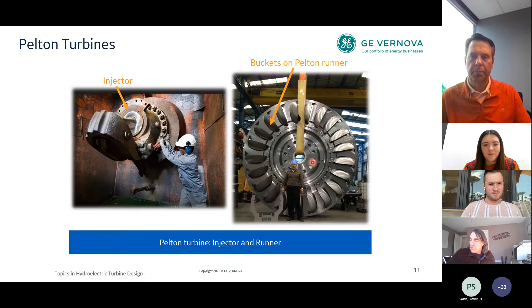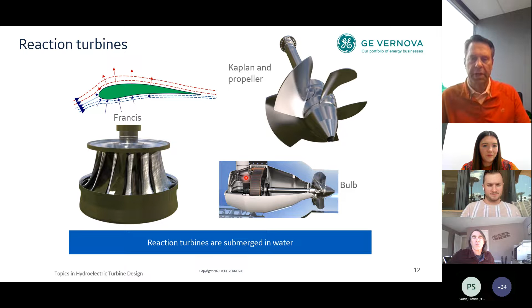This is the reaction turbine. You have pressure coming on the front side and on the back side, so it's a pressure differential that turns it, just like a wind turbine when wind blows. The water hits the Francis turbine, the Kaplan propeller, or the bulb, which turns and rotates the shaft, which turns the generator. Those are the reaction type runners.